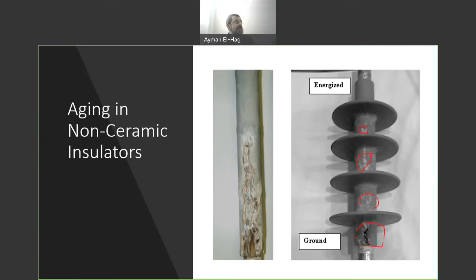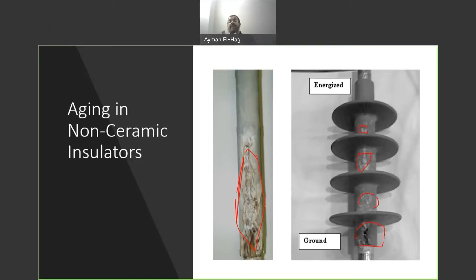This is a rod of a silicone rubber insulator and you can clearly see damages that happened to the rod. So, before we use the material or the insulator in the field, we have to make sure that they can withstand such arcing on their surface.